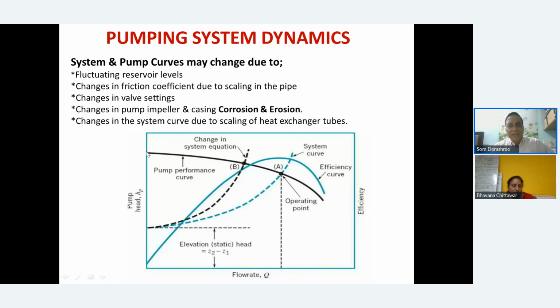Now, you know that this is my pump performance curve. This is my system curve. This is the elevation. Let's say I have to send the water to the top floor. So this is the static height that I have to raise this water. And then as the flow increases, there will be friction losses. So the head requirement will go like this.